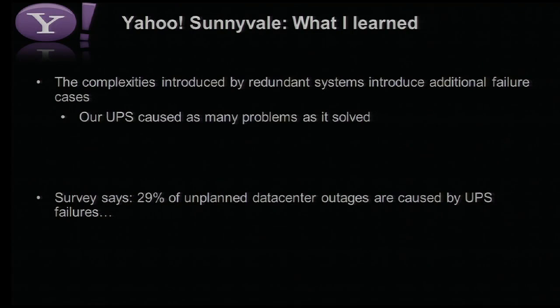So what did we learn? The complexities introduced by adding all of these redundant systems actually introduce additional failure cases. Our UPS caused as many problems as it solved. I would say more. Recent surveys said 29% of unplanned data center outages are caused by UPS failures.